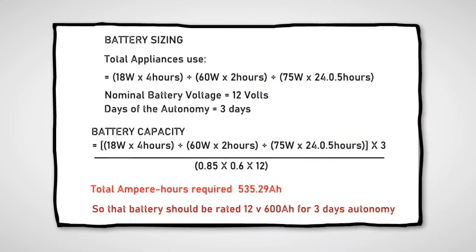This is the computation for battery sizing. Calculate the total watt-hours per day used by appliances, and divide the total watt-hours per day by 0.85 for battery loss. Then divide your answer by 0.6 for depth of discharge. Divide again by the nominal battery voltage. Finally, multiply your answer by the days of autonomy — the number of days you need the system to operate when there is no power produced by PV panels. This gives you the required ampere-hour capacity of the deep cycle battery.